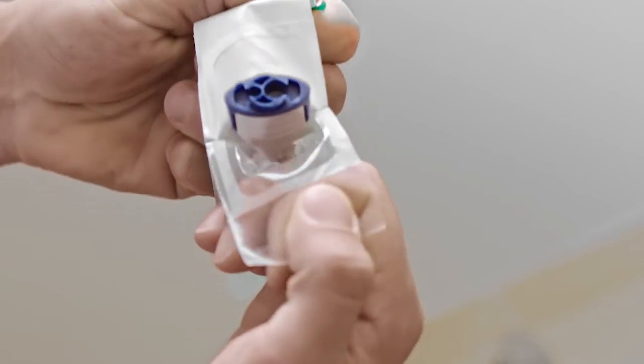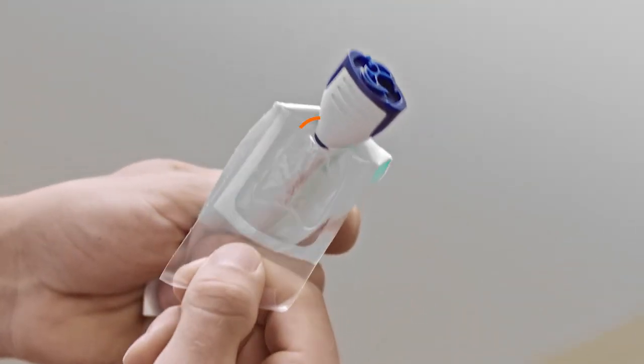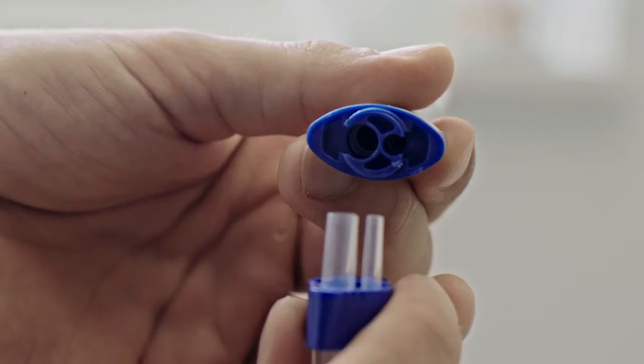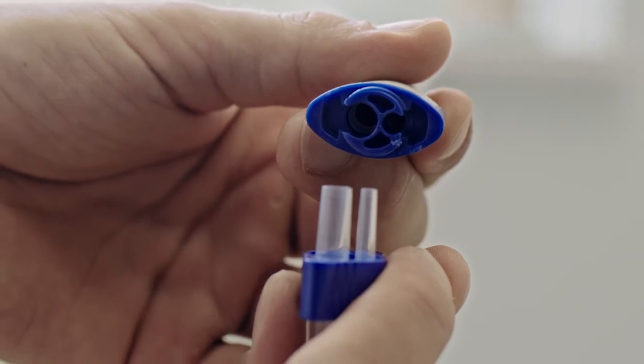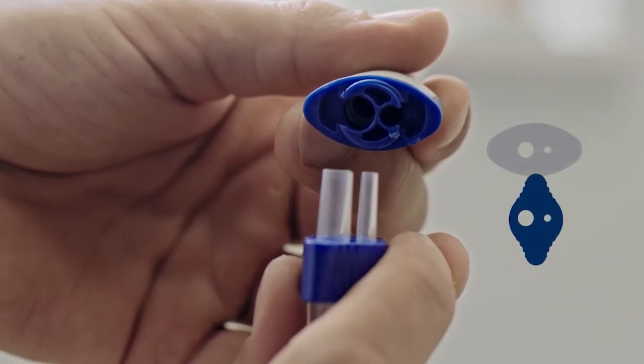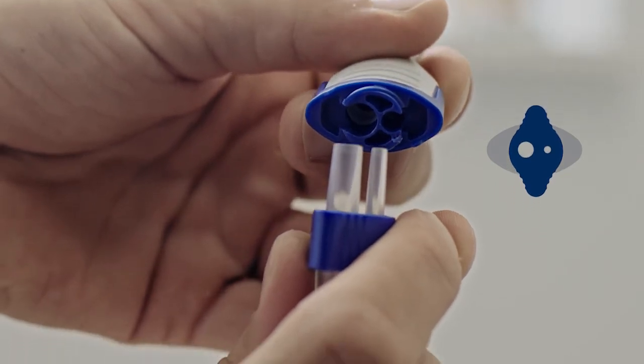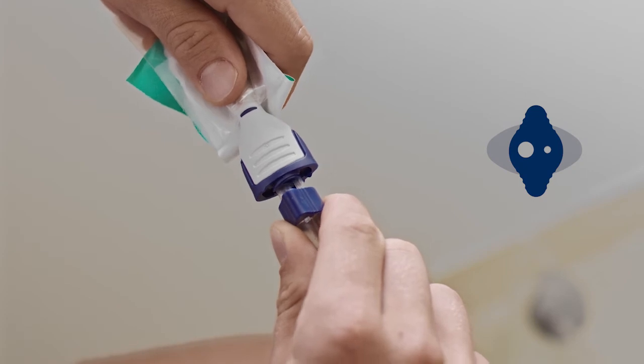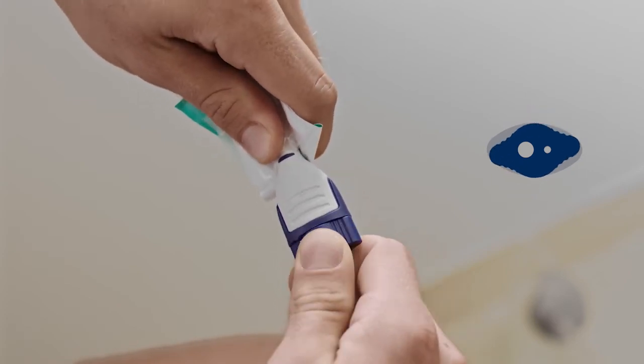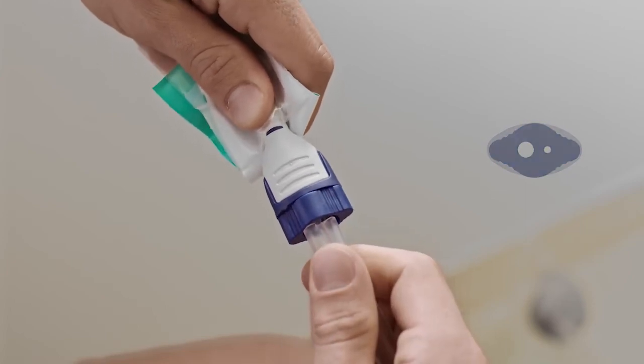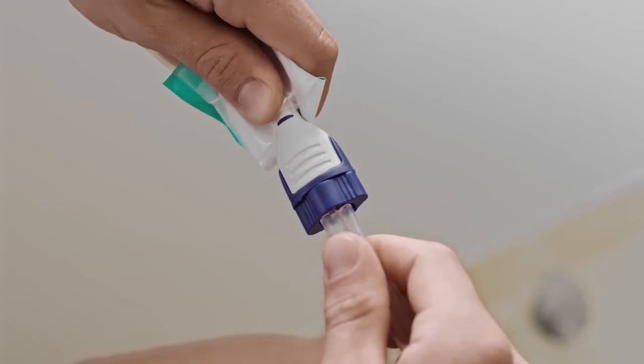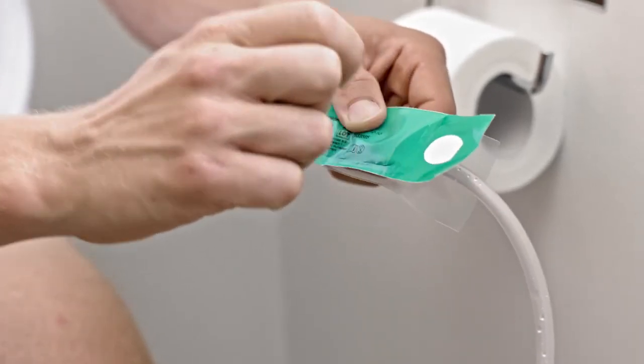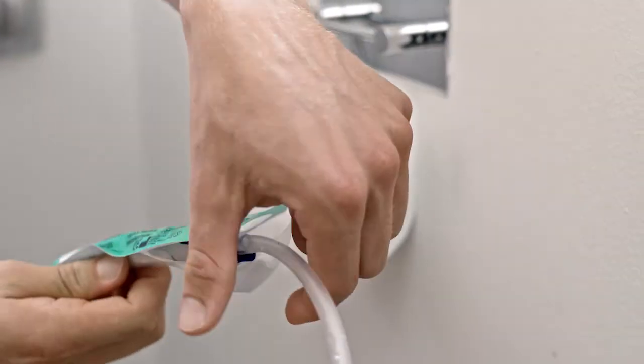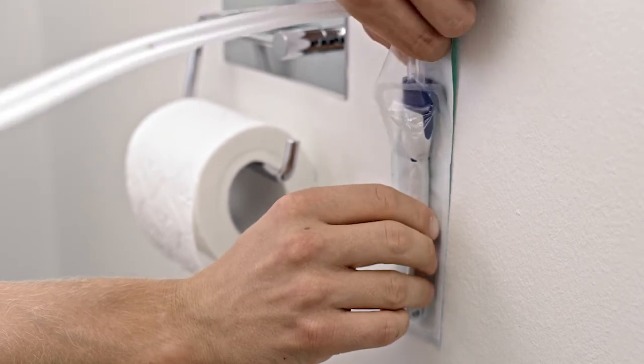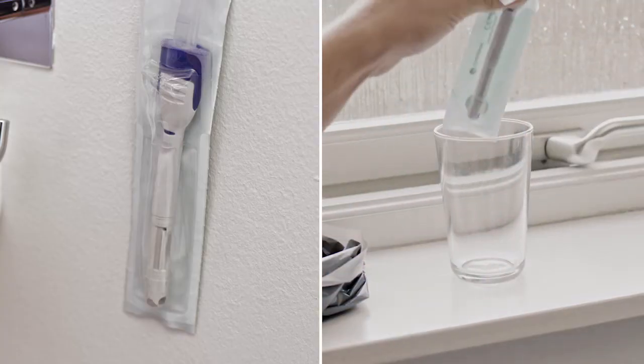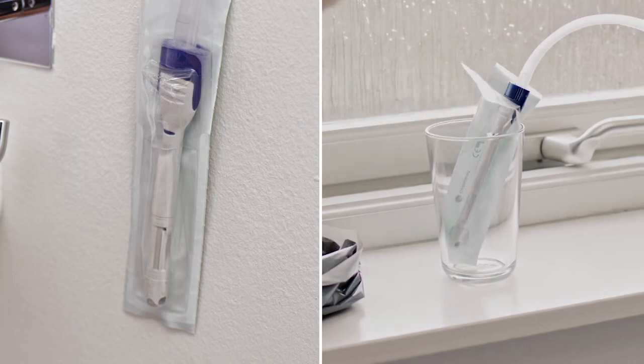Now slightly open the balloon catheter packaging, approximately to the blue line or about 2 to 3 centimeters. Connect the blue connector on the tube to the balloon catheter by aligning the big tube with the big hole and align the small tube with the small hole. Make a cross, push together, and then twist gently clockwise to lock. Gently tug the connector to make sure it's connected. You can attach the packaging to a surface by peeling off the adhesive dots. Alternatively, you can place the balloon catheter with the packaging in an empty glass to contain any spillage.